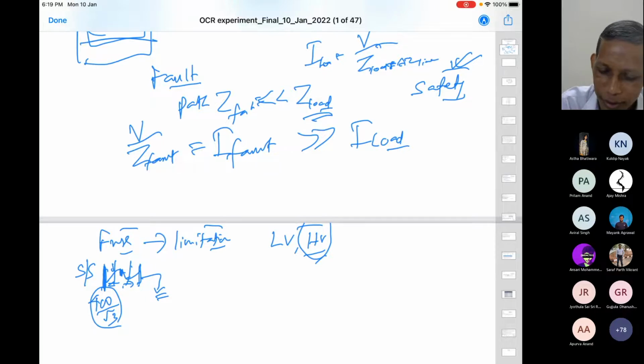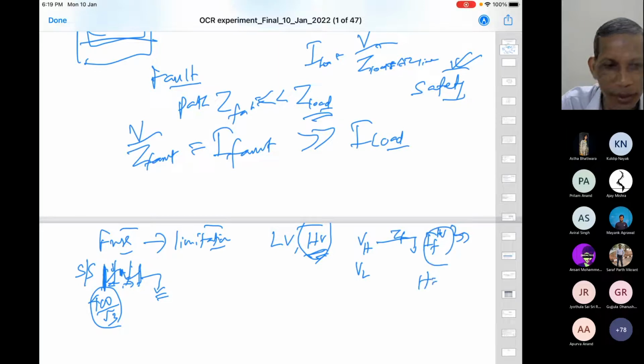Furthermore, in a high voltage system, this is the high voltage, and we have V low voltage. Now the impedance remaining the same at the fault point, the corresponding I fault in case of a high voltage system becomes much higher compared to the low voltage system. But again we square it to find the H, same element. Again we square it, H equals I square RT. So therefore the I square term will be much higher.